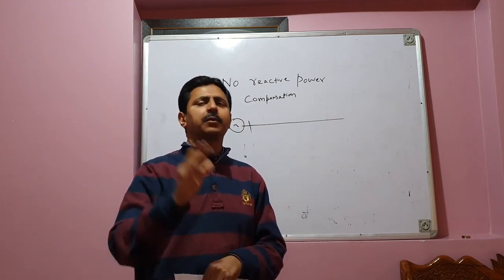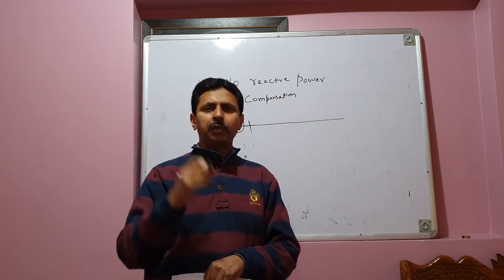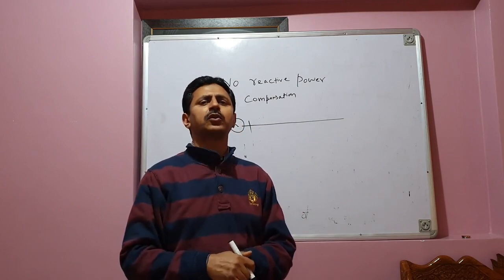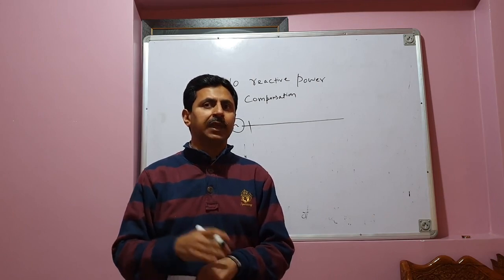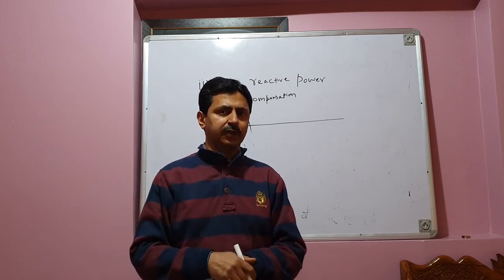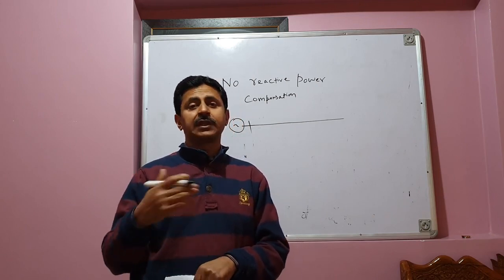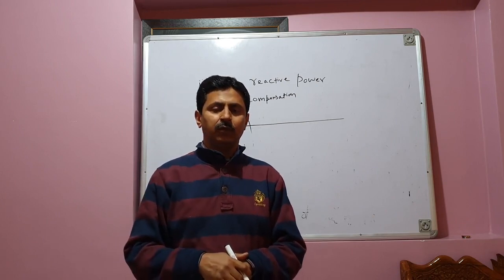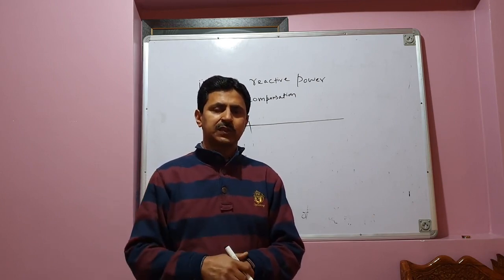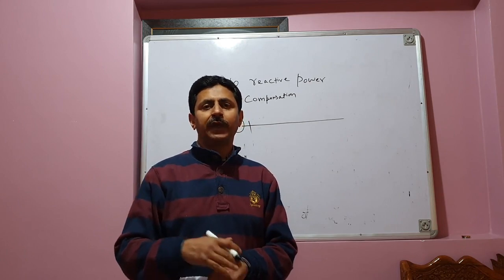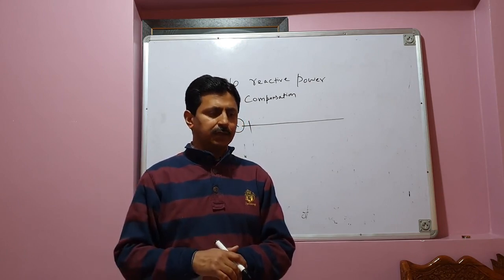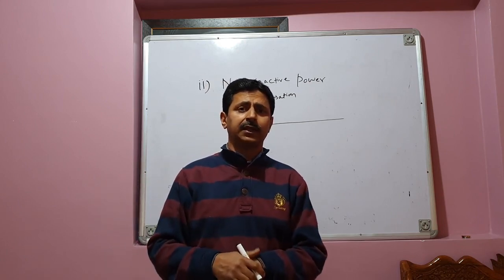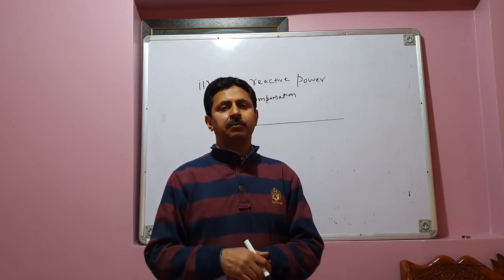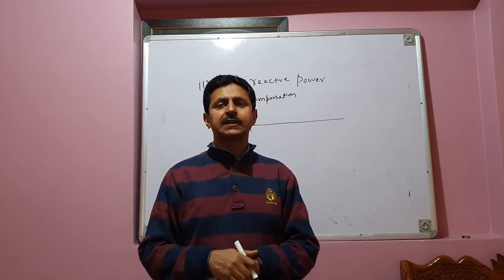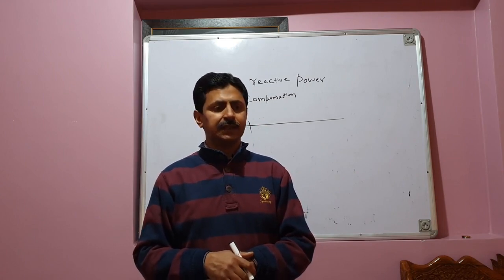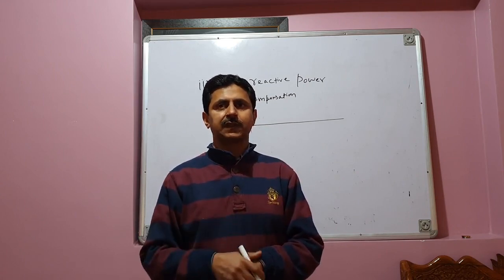Let's forget about line reactance. Load demands the reactive power. This reactive power flows over the line, and you have to compensate for this reactive power for improving the stability of the system, for damping the power oscillations, and for providing the voltage support and all that. Those of you who have done that FACTS course with me in MTech first semester already discussed these points in detail. It was a very useful discussion at that time.